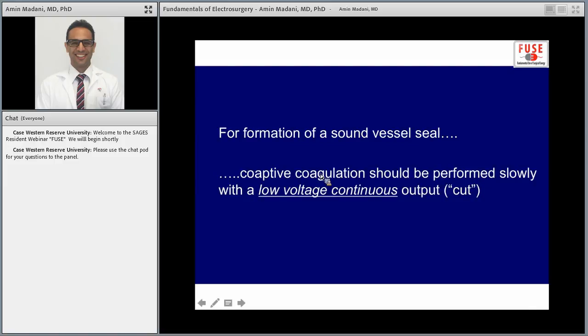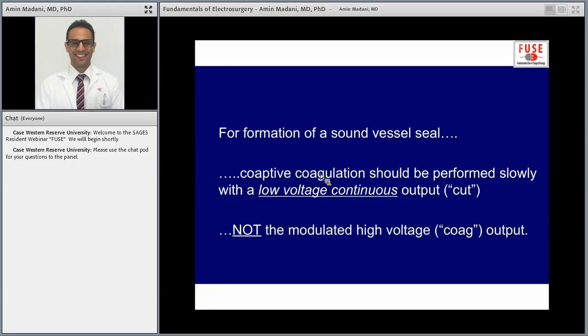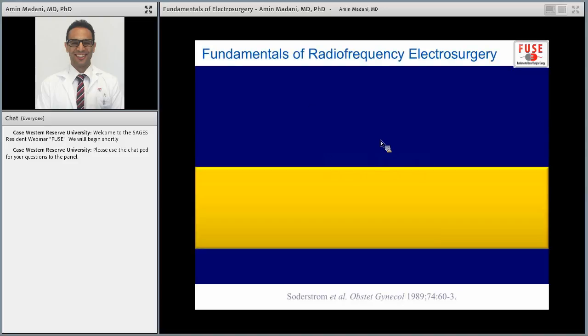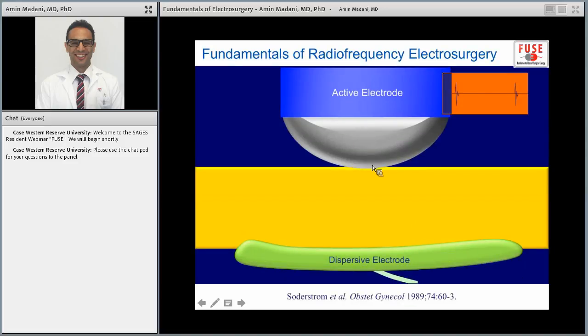The best way to do that is to use a low voltage waveform like cut. Why is that? Let's demonstrate that with the schematic here. So here we have the dispersive electrode, and here we have the active electrode, and this is the tissue. And then we activate. Let's say we're using coag, so interrupted waveform, high voltage. We start activating. You start getting a lot of desiccated tissue here superficially. But the problem is this desiccated tissue is an insulator. It's not a conductor anymore. So this tissue beneath will not get any thermal effect. There won't be any tissue effect there. So what you end up having is a heterogeneous area of desiccation. It's not a homogeneous vessel seal anymore when you're on your pickup.